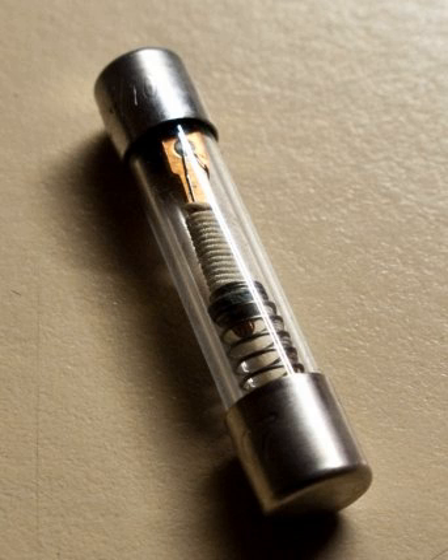Cartridge fuses may list the following speeds. Fuse selection depends on the load's characteristics. Semiconductor devices may use a fast or ultrafast fuse as semiconductor devices heat rapidly when excess current flows. The fastest blowing fuses are designed for the most sensitive electrical equipment, where even a short exposure to an overload current could be very damaging. Normal fast blow fuses are the most general purpose fuses.